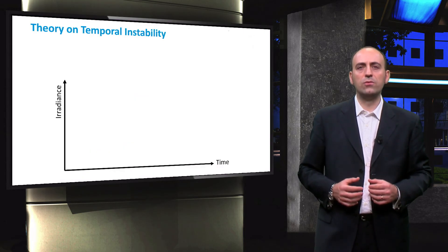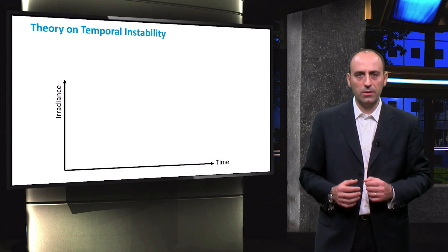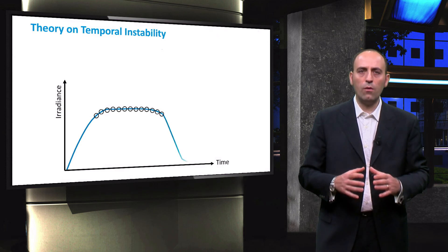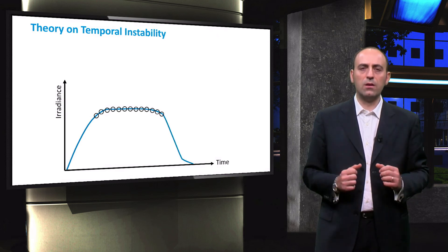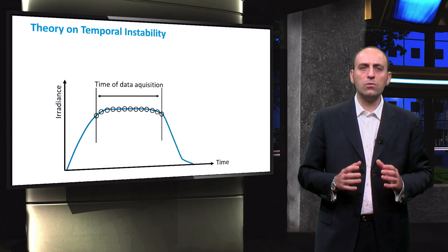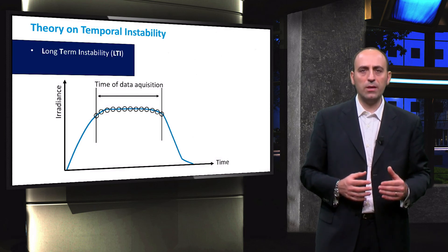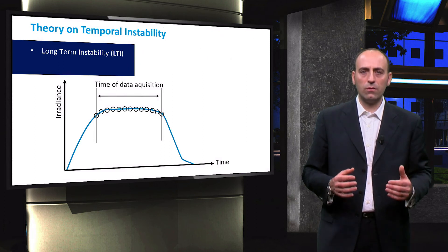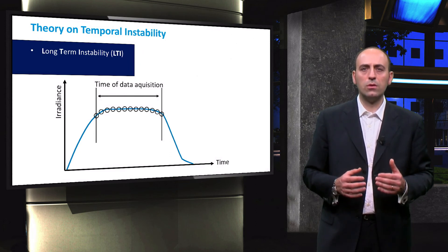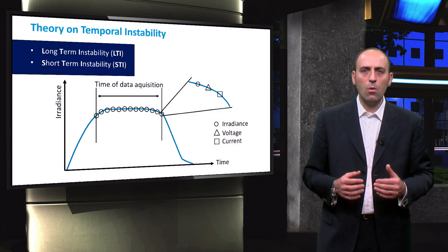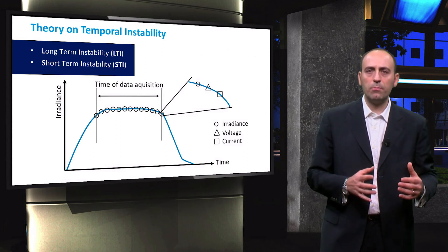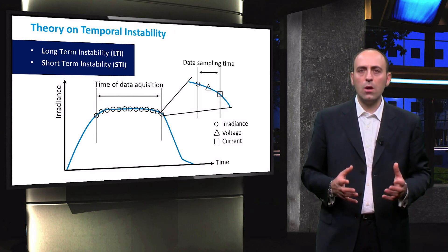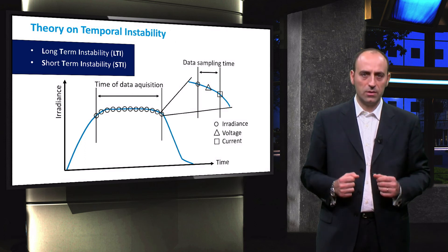The third and last category to determine is the temporal stability. The general method is to measure the irradiance of the simulator over a specific time period. According to this time interval, we talk about long-term instability, or LTI, when we consider the entire time period of interest. Or we can talk about short-term instability when we consider the instabilities between measurement points of irradiance, current and voltage — in other words, when we consider the data sampling time of a data set.